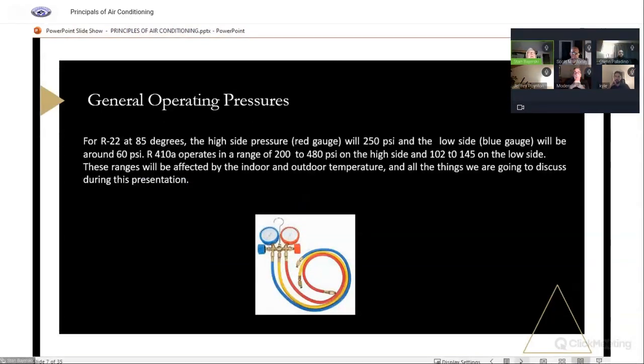So general operating pressures in an air conditioning system with R22 at 85 degrees, we'll say that's kind of normal summer temperature, maybe a little higher. The red gauge, the high side pressure, will be around 250 psi, and the low side, the blue gauge, will be around 60. And R410A, it's going to range on the high side, on the low side, I'm sorry, high side from 200 to 480, and on the low side, 102 to 145.